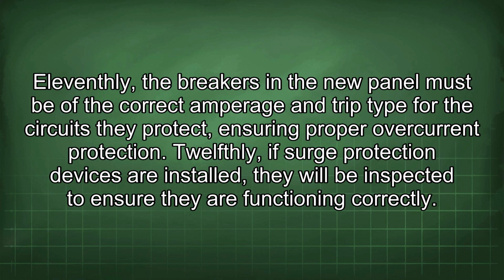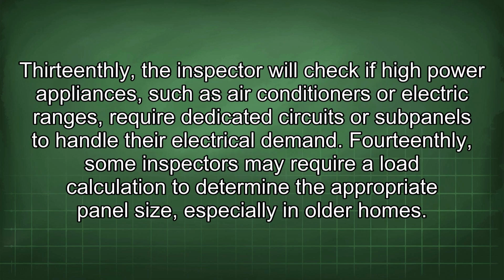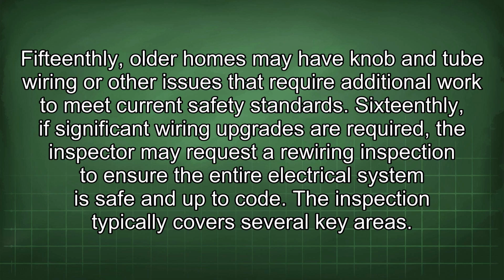Twelfthly, if surge protection devices are installed, they will be inspected to ensure they are functioning correctly. Thirteenthly, the inspector will check if high-power appliances, such as air conditioners or electric ranges, require dedicated circuits or subpanels to handle their electrical demand. Fourteenthly, some inspectors may require a load calculation to determine the appropriate panel size, especially in older homes. Fifteenthly, older homes may have knob and tube wiring or other issues that require additional work to meet current safety standards. Sixteenthly, if significant wiring upgrades are required, the inspector may request a rewiring inspection to ensure the entire electrical system is safe and up to code.